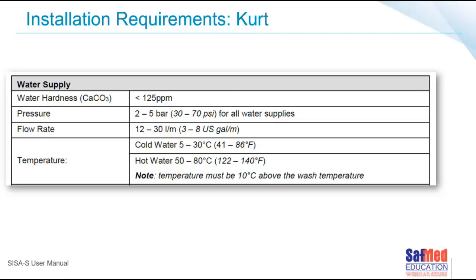We can't just throw the ultrasonic cleaner in a corner and hope for the best. The amount of space around it matters. The type of water, the quality of the water, the temperature of the water. If the water is too cold, what will happen? The machine will first of all give you an alarm if it's a fully automated brand and model. If it's semi-automated, where you fill up your own water and you don't maintain the water temperature stated in the instructions for use, it's going to affect the cleaning of the instruments, because the enzymatic detergent that you use needs a certain temperature to activate and clean effectively. So too cold water won't work.